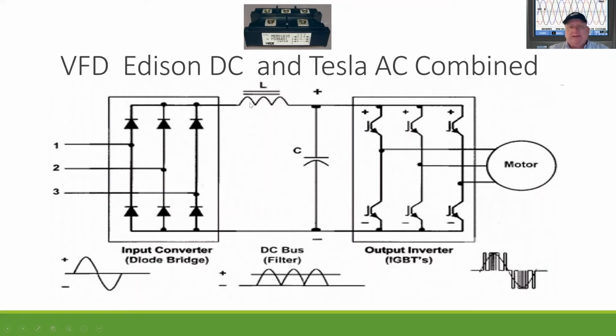They also put in these line reactors, link chokes, different things. It's basically a coil, which reduces current flow. It wants to hold it back a little bit compared to what the voltage does. So what that does is, again, help us smooth this DC power, because we're wanting to get firm DC power.